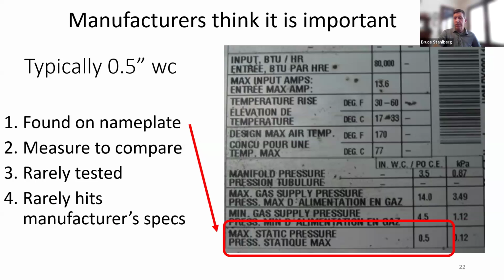But the manufacturers definitely think it's important. They put it on the nameplate. More manufacturers are taking a closer look at this because it's found on the nameplate, but it's rarely tested in the field, and I think anyone in the HVAC industry would confirm that. We do a lot of another measurement called temperature rise, but rarely is static pressure measured. And it rarely hits the manufacturer's specifications. Most furnaces are rated at 0.5 inches of water column.